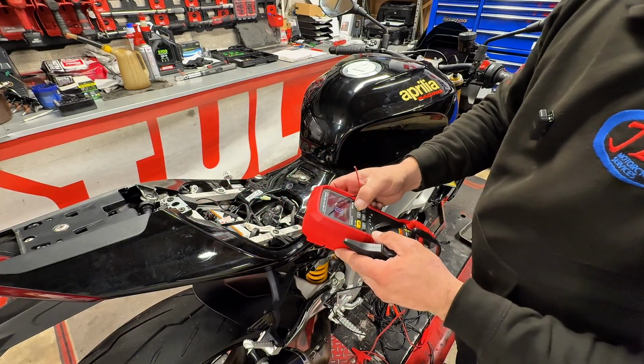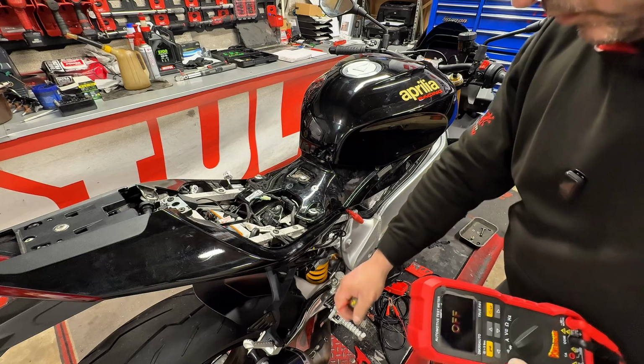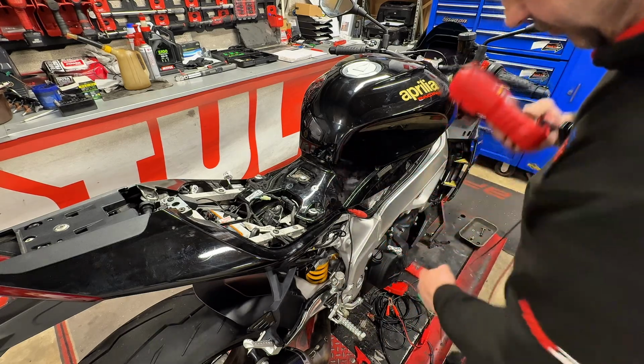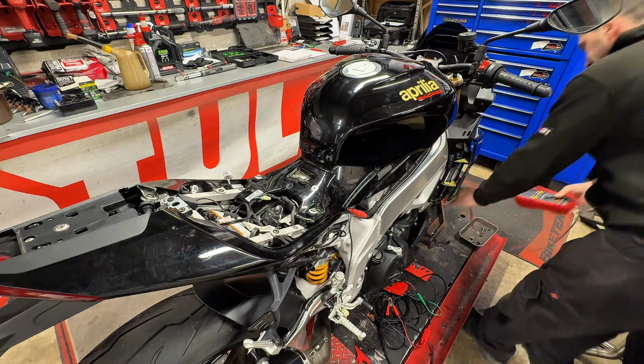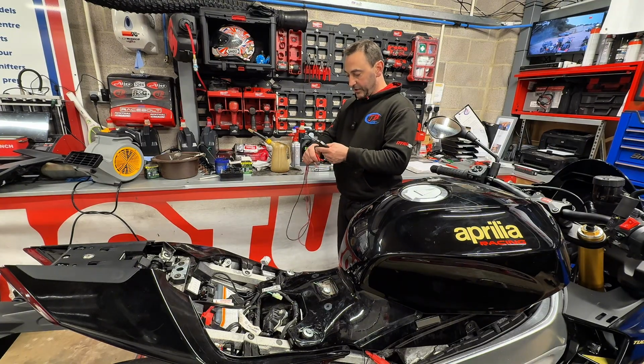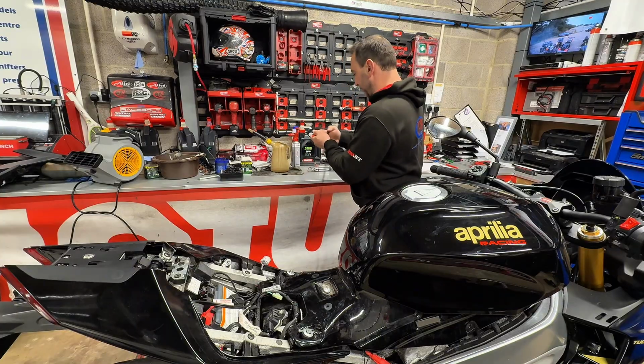So that's that test done. That basically says that the singular wires going up to the sensor are absolutely fine. So that means it's highly likely that it is the actual sensor that is at fault.